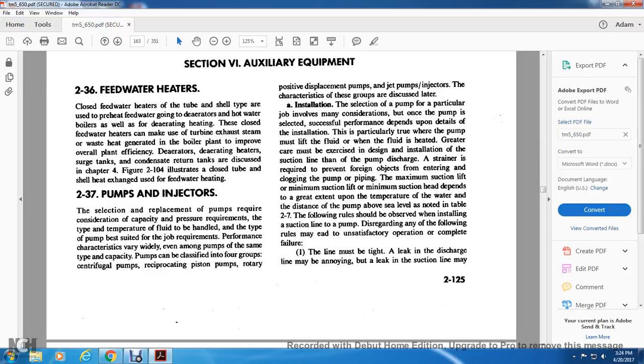Installation. Selection of the pump is, of course, the first consideration for the job involved, but once the pump is selected, performance depends upon the details of installation. This is particularly true when the pump must lift the fluid. When the fluid is heated, the greater care must be exercised. The design and installation of the suction line is critical, as is the discharge line. A strainer is required to prevent foreign objects from entering and clogging the pump and piping. The maximum suction lift depends to a great extent upon the temperature of the water and the elevation of the pump above sea level, as noted in Table 2-7.